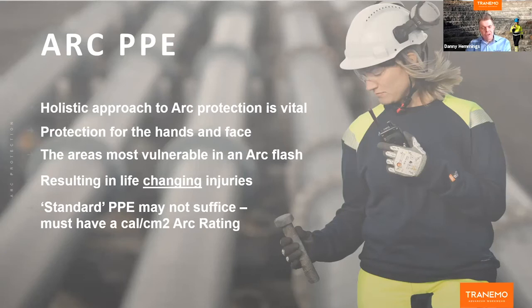And don't just rely on the fact that you have standard PPE. You have a visor or face protection or hand protection that is PPE rated. That may not suffice. It's important that we're talking about PPE and head protection that is arc rated, that has a protection level for thermal energy expressed in calories per centimeter squared.